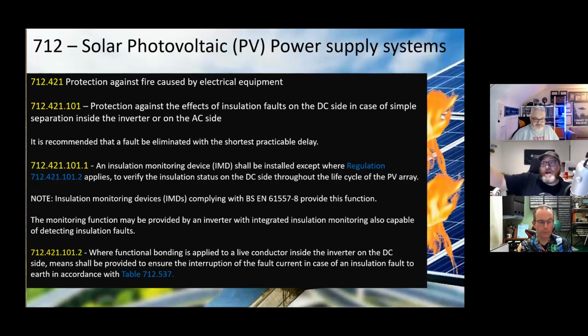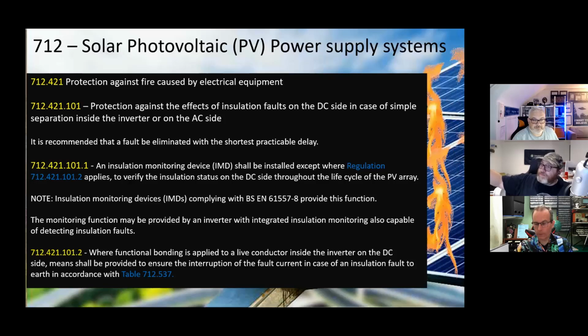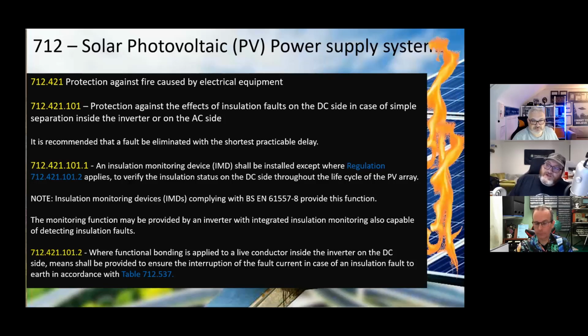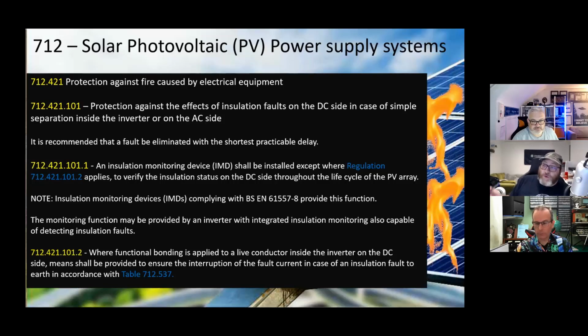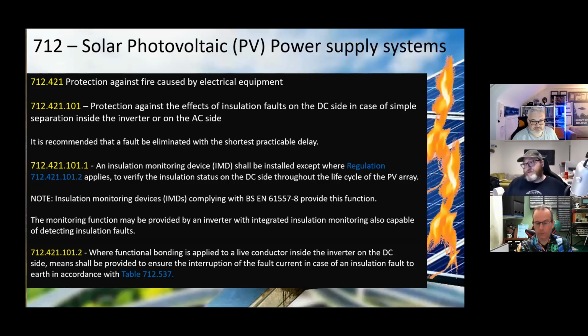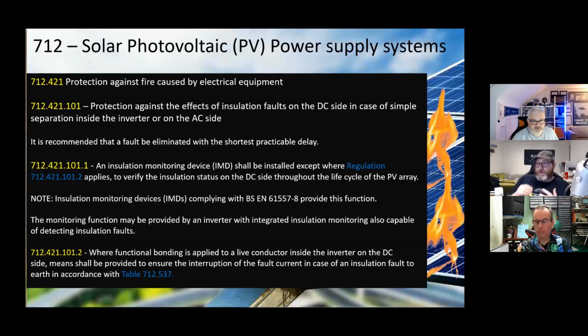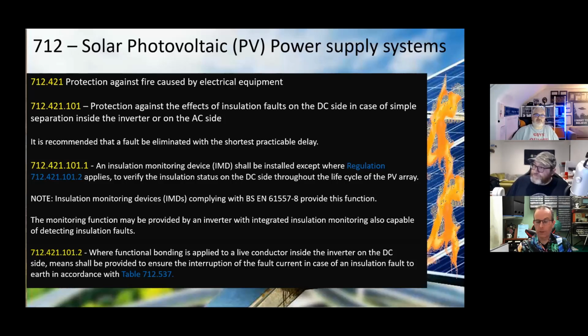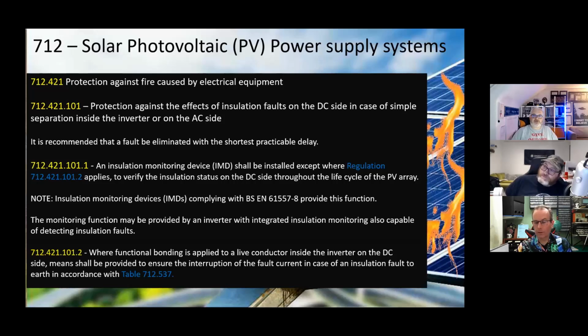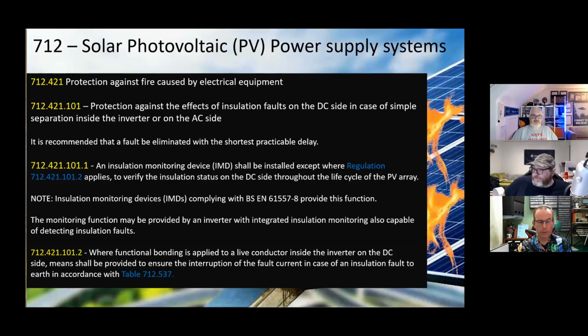Okay, the alternative to the IMD is if there's functional bonding. Functional bonding. This is another term. Applied to live conductor inside the inverter on the DC side means to be provided to ensure the interruption of the fault current in a case of insulation fault to earth in accordance with table 712.537. So that's the functional bonding, because functional earthing was always if you break the earth, the equipment stops, it doesn't work. It needs it for the operation of the equipment, i.e. balance load, three-phase motor or something.